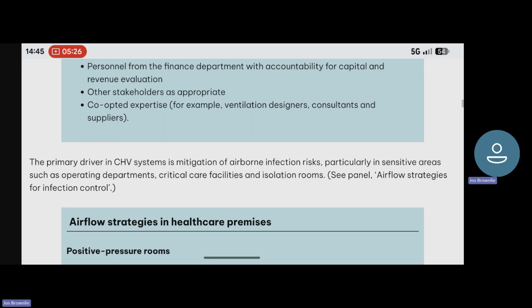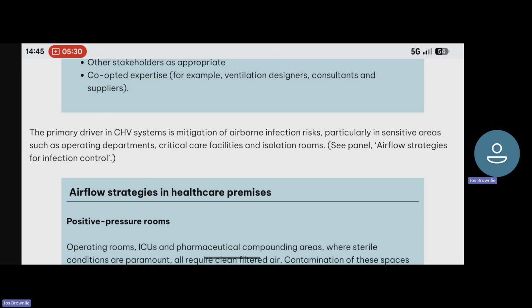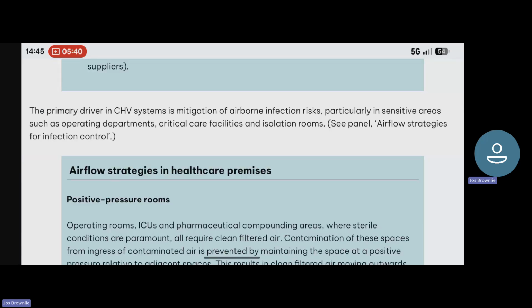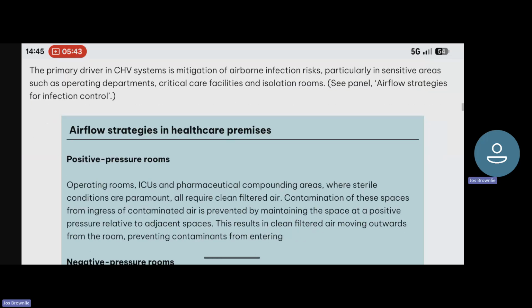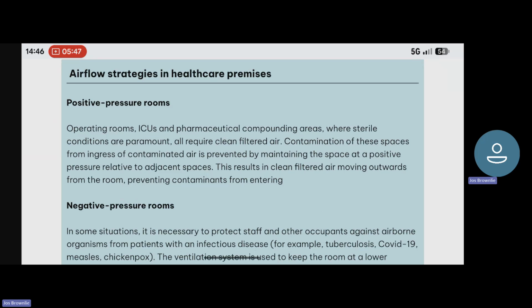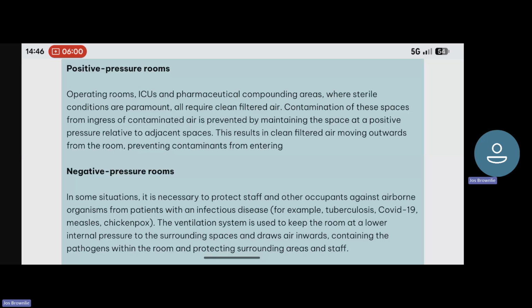The primary driver in CHV systems is mitigation of airborne infection risks, particularly in sensitive areas such as operating departments, critical care facilities, and isolation rooms. Airflow strategies in healthcare premises, positive pressure rooms, operating rooms, ICUs, and pharmaceutical compounding areas where sterile conditions are paramount, all require clean filtered air. Contamination of these spaces from ingress of contaminated air is prevented by maintaining space at positive pressure relative to adjacent spaces. This results in clean, filtered air moving outwards from the room, preventing contaminants from entering.